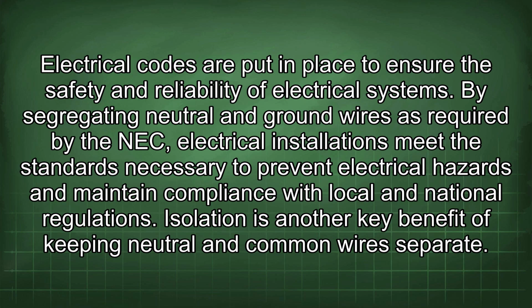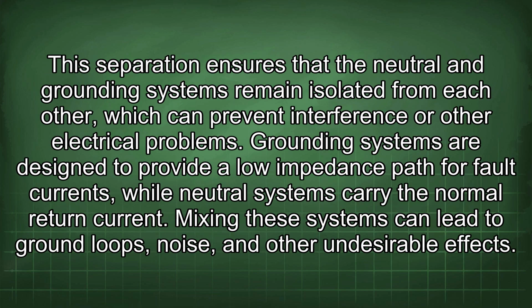Isolation is another key benefit of keeping neutral and common wires separate. This separation ensures that the neutral and grounding systems remain isolated from each other, which can prevent interference or other electrical problems. Grounding systems are designed to provide a low impedance path for fault currents, while neutral systems carry the normal return current. Mixing these systems can lead to ground loops, noise, and other undesirable effects.